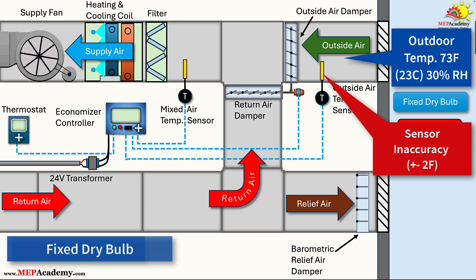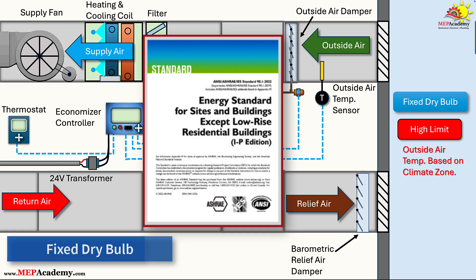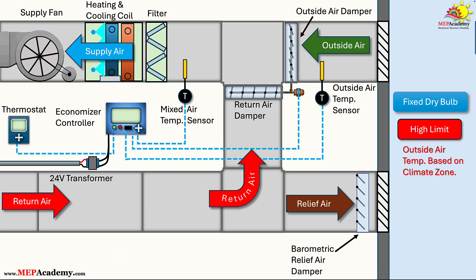Sensor inaccuracies, typically around ±2°F, can exacerbate these issues, resulting in higher energy use. In humid climates like Zone 1A, such as Miami, this could lead to unacceptable indoor humidity levels if not carefully set. Additionally, energy standards like ASHRAE 90.1 restrict its use in some warm, moist climates where it might increase mechanical cooling demands. Optimal set points vary by climate – 69°F for humid zones like 1A–5A, up to 75°F for drier zones like 3C, 6B, or 8.